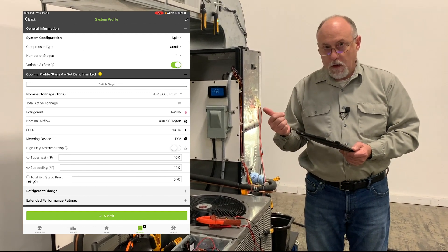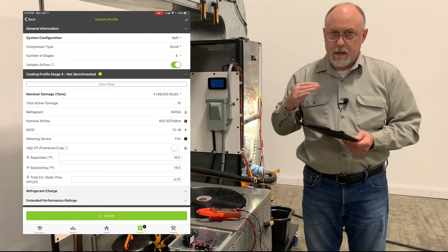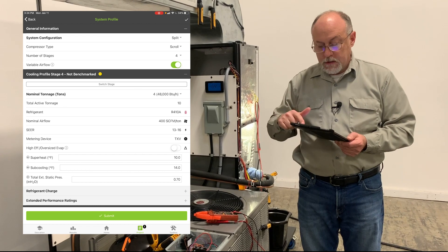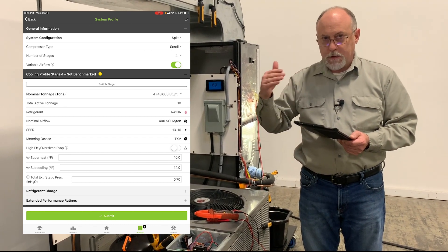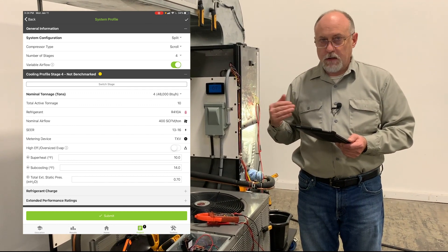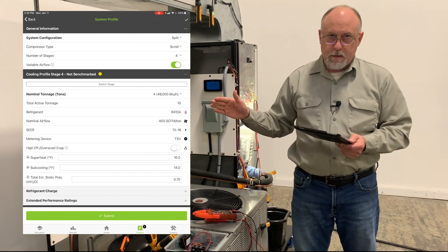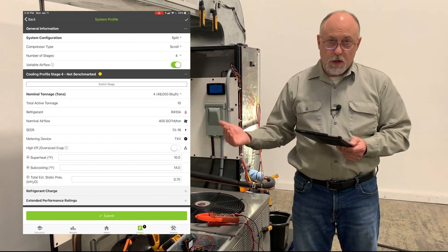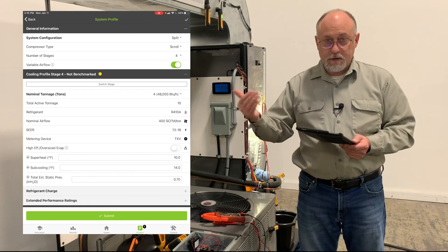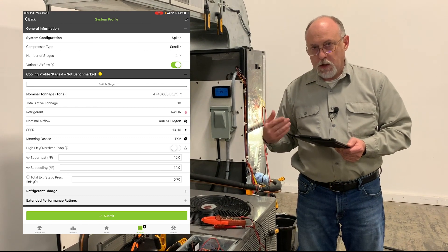You can set it up with variable airflow — meaning as you ramp up your capacity, your airflow changes, which is more what we see in multi-stage systems — or you can have it set up with constant airflow, which is how it defaults. With constant airflow, as you layer up the number of stages, it recalculates the target temperature split, airflows, and all that for each stage independently. You can also have separate refrigerants for each stage. So if you're doing a four-stage unit and you're converting two stages from R22 over to Bluon, you can have two stages R22 and two stages Bluon. As you store those benchmarks and profiles in the cloud, all that data stores with it. There's a lot of breadth and depth to the multi-stage and multi-circuit modes.